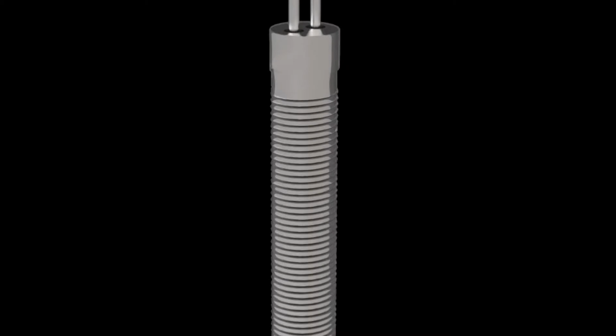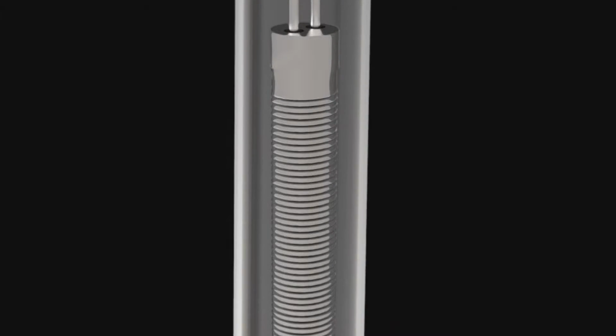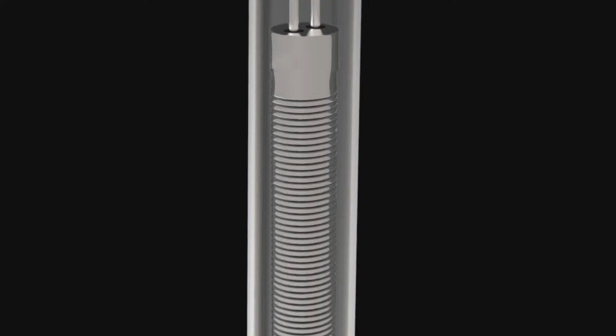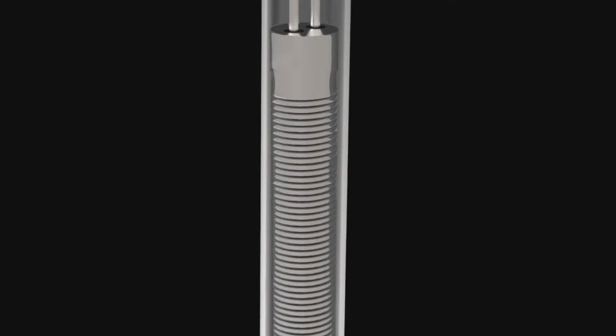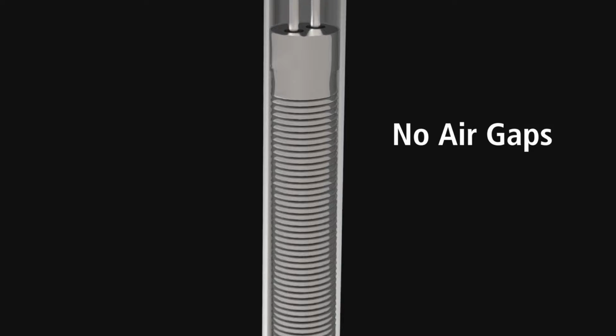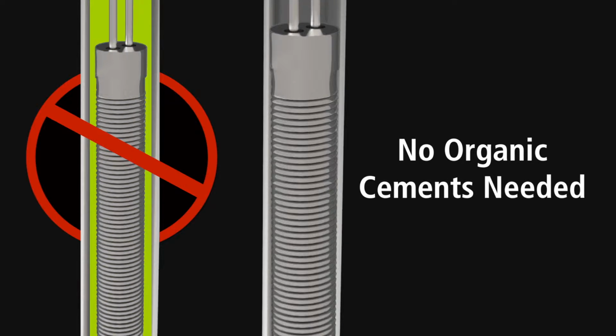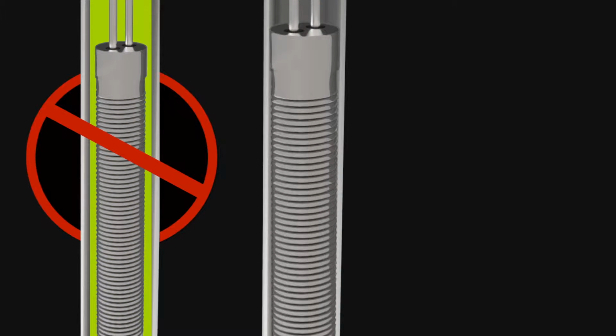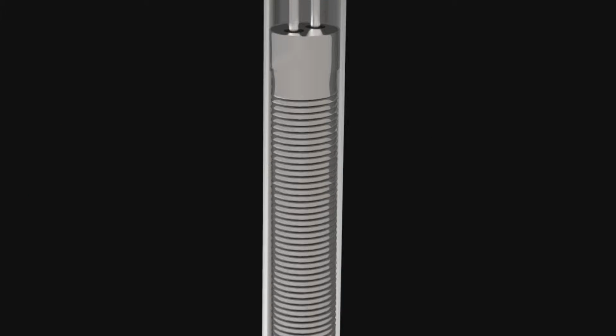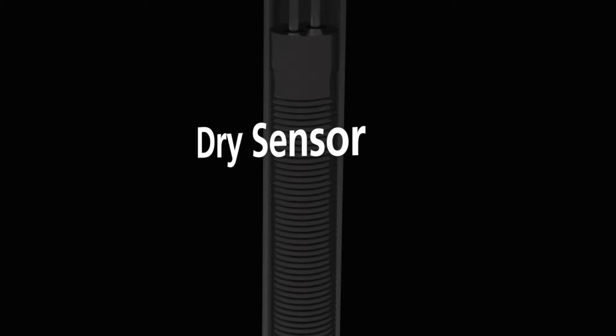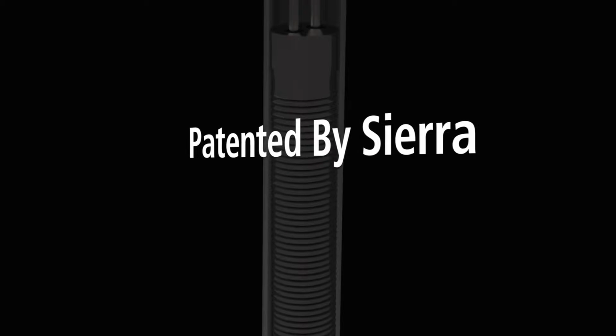Through a proprietary, highly controlled manufacturing process, a metal sheath is tightly formed on the mandrel and wire assembly to be in such intimate contact that no air gaps exist and no organic filler cements are needed. This new sensor was literally all metal. In contrast to wet sensor design, this innovative cement-free sensor is known as a dry sensor. It is patented by Sierra and is brand named DrySense.